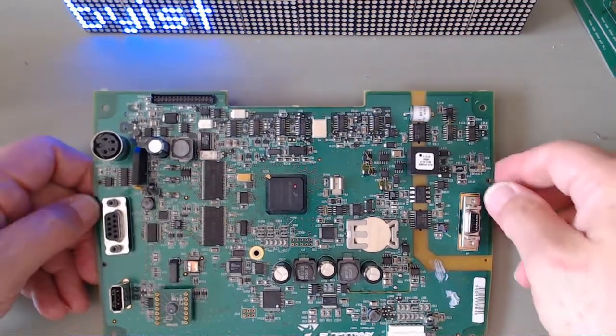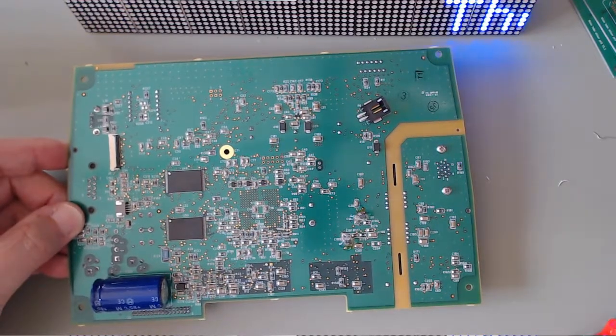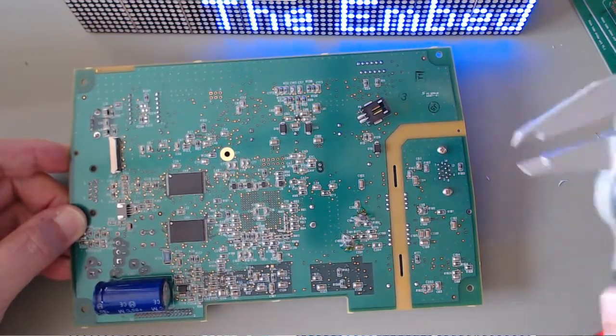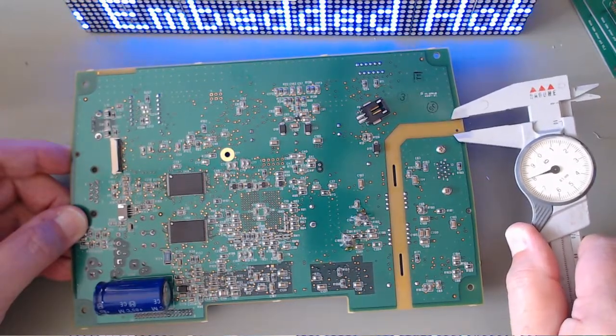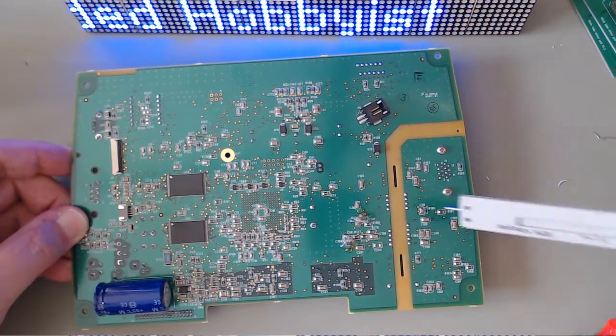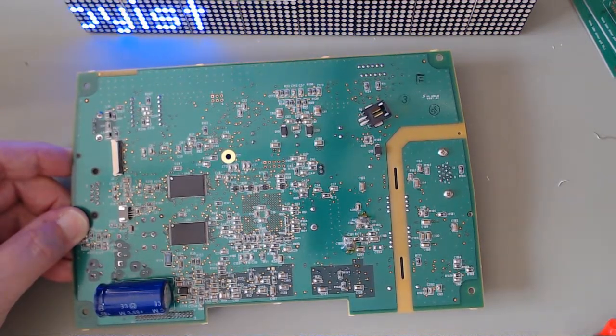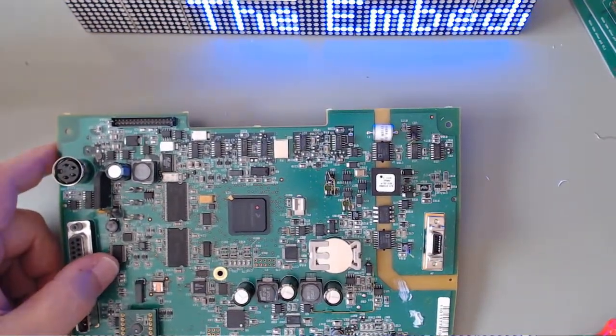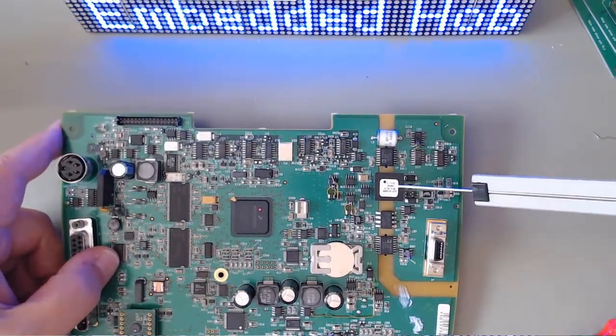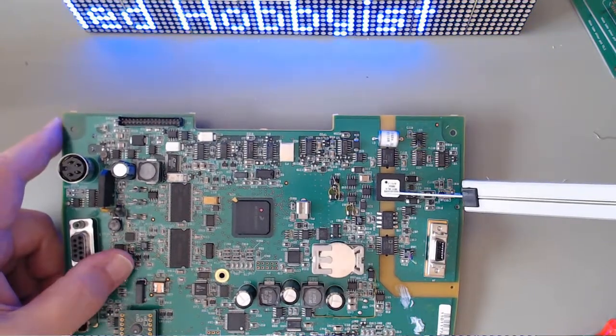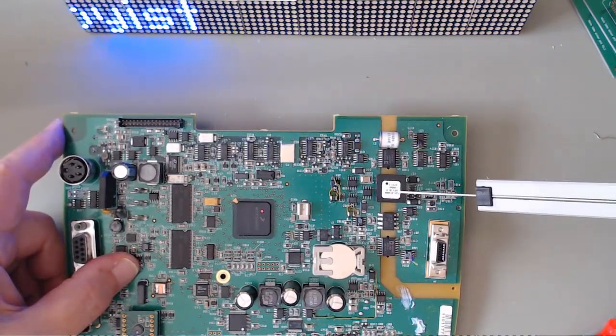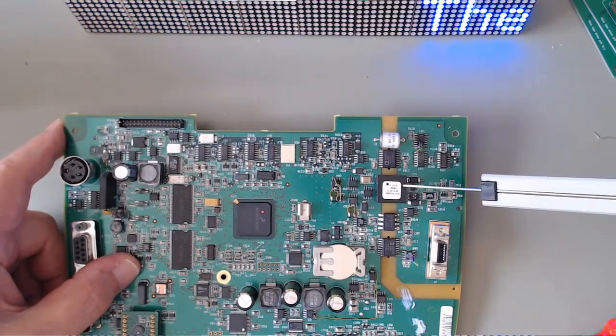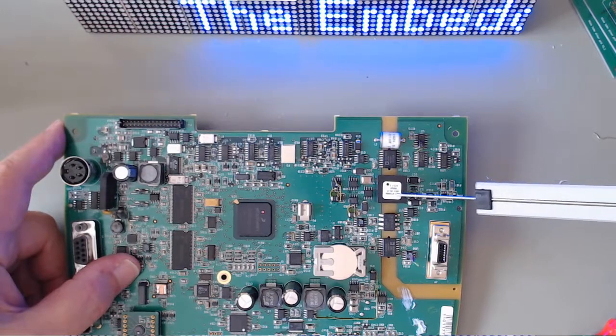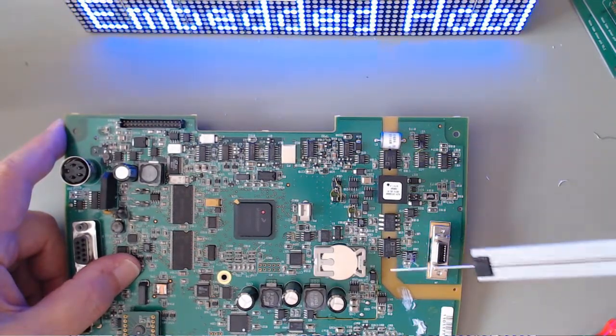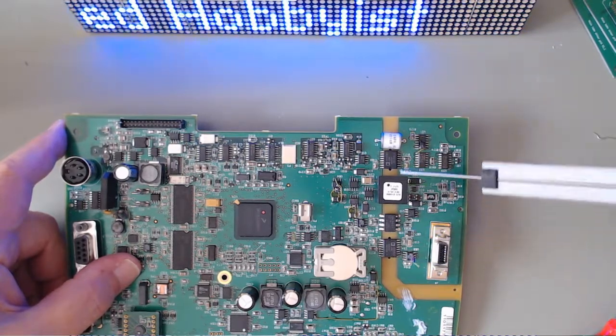And sorry, it's sticking in my throat. If you turn it over and look on the other side, you can see the isolation is still maintained, the clearance is still maintained at 8mm, and then you can see the slot for those components. Now we'll have a look at the data sheets in a minute, because I can't find a data sheet on the power supply, but I know it's a 5V DC converter, and it's a medical grade high reliability converter, and so the isolation on that will be as good or better than what's on these chips.